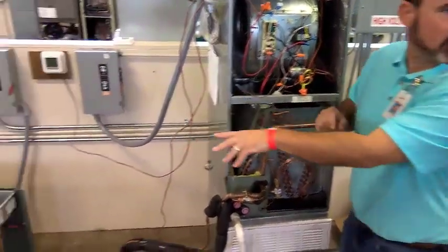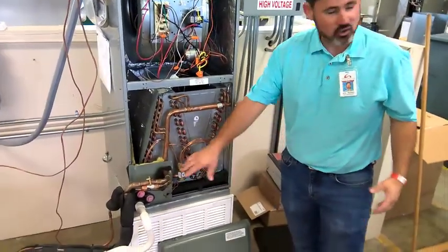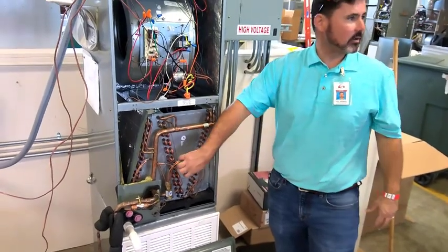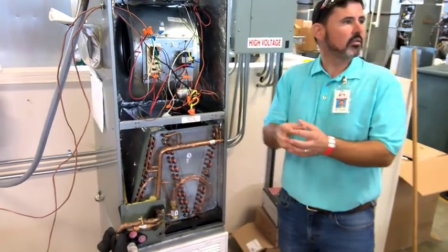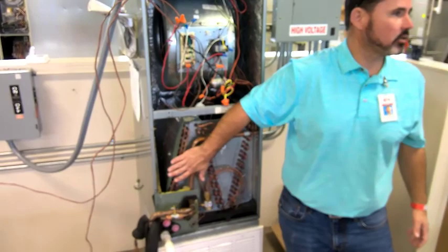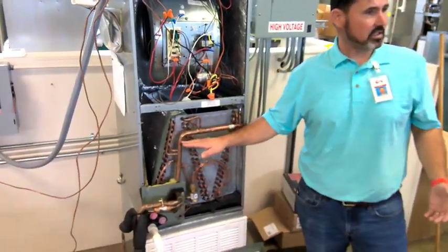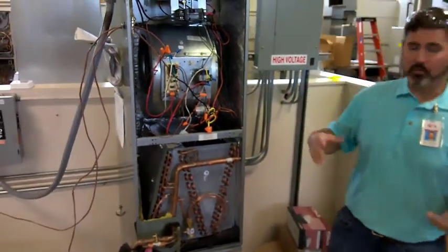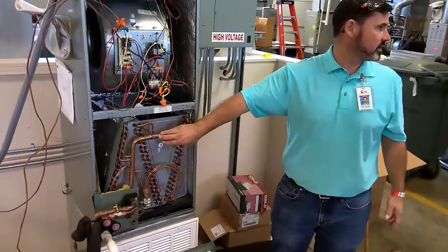Outside, I got my pressure high on that condenser so I could get rid of heat. When I came inside, I dropped that pressure drastically so that I could absorb it. Now that refrigerant's colder than the outside air, or the air circulating through it, so now it's absorbing heat. If I have 75-degree air going across a 40-degree coil, now I have a temperature difference of 35 degrees, right? And heat moves hot to cold, so that heat's going to move from my 75-degree air into my 40-degree refrigerant.